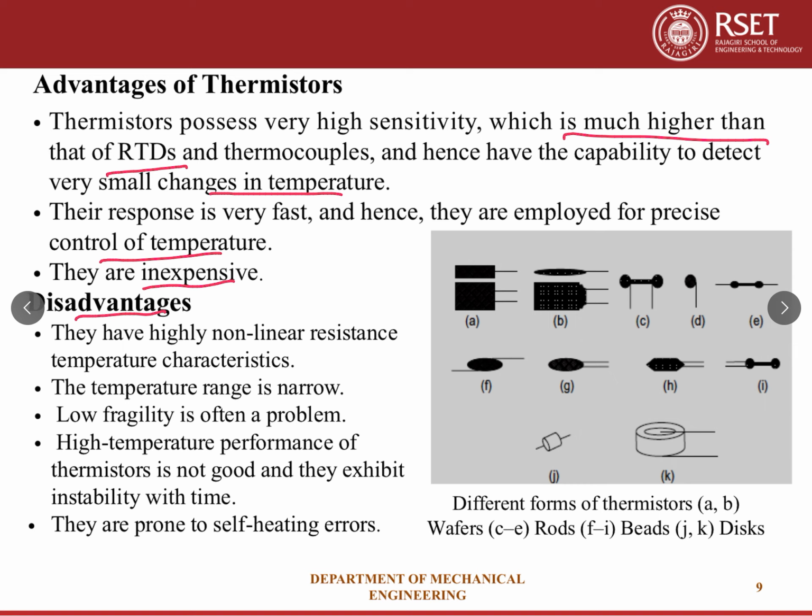Some disadvantages. They have highly non-linear resistance temperature characteristics. The temperature range is narrow. Low fragility is often a problem. High temperature performance of thermistors is not good and they exhibit instability with time. They are prone to self-heating errors. These are the disadvantages of thermistors.